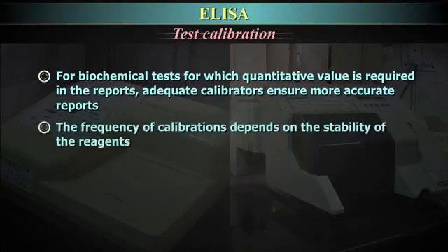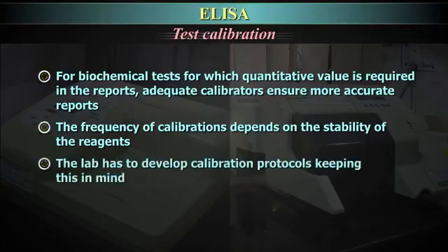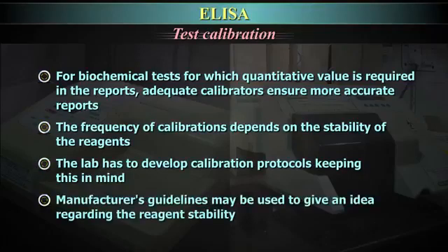The frequency of calibrations depends on the stability of the reagents. The lab has to develop calibration protocols keeping this in mind. Manufacturers' guidelines may be used to give an idea regarding the reagent stability.